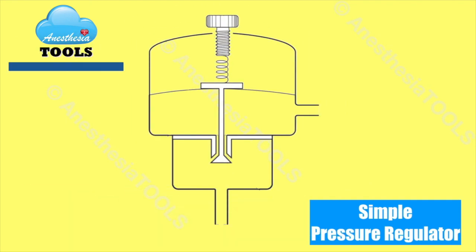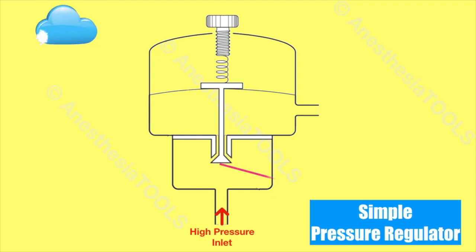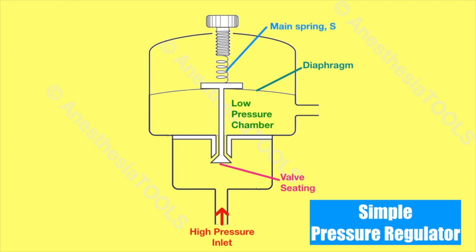Now let us see the working principle of a pressure regulator. The gas from the cylinder passes through a filter and the inlet into the high pressure chamber. The gas then passes through the valve into the low pressure chamber. The increased pressure in the low pressure chamber tends to distend the diaphragm, the force of which is opposed by the tension in the spring.